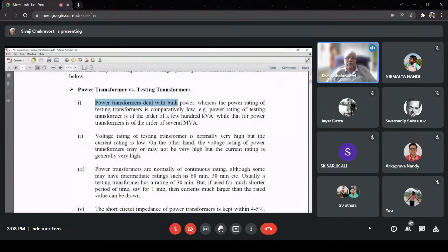So most importantly, you have to understand that power transformers deal with bulk power. They are transmitting power of the order of hundreds of megawatts, at least, if not 50, 60 megawatts of that range. But testing transformers in the laboratory are not supplying any power. What they are doing is testing the insulation of an equipment. Therefore, the power rating of a testing transformer is very low. Just for your information, this is again a practical tip. Typically, the secondary, that means the high voltage side of the testing transformer, current rating will be typically of the order of not more than 1 ampere, even less probably.